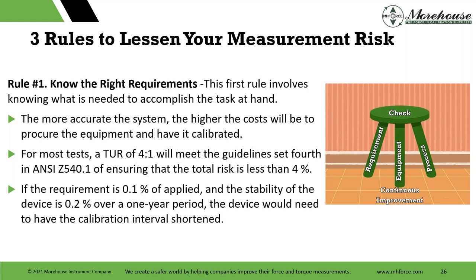ANSI Z540.1 would ensure that the total risk — two sides to each tail of a normal probability distribution — is less than 4%. My other note: if the requirement is 0.1% of applied and the stability of a device is 0.2% over a one-year period, anyone think that's going to be good? We see this quite a bit — customers send stuff in and say they want adjusting if it doesn't meet 0.1%, and the PFA is higher than 2%.